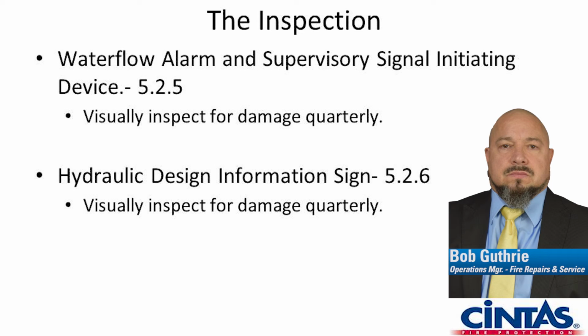Normally, the hydraulic calculations placard will be hanging from the riser on the chain. It's probably in the neighborhood of 4 to 5 inches wide and about 7 inches tall. That hydraulic calculation placard tells the inspector the criteria that was used when the sprinkler was installed. It will say that it was light hazard, ordinary hazard, high hazard, extra 1, extra 2. It will tell the water demand for the sprinkler system.